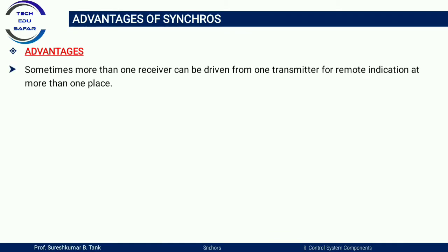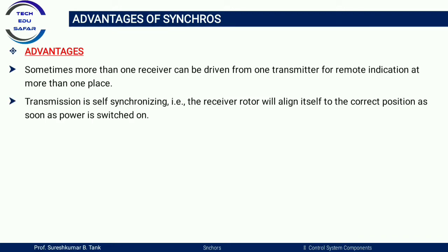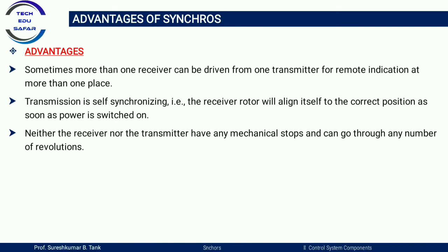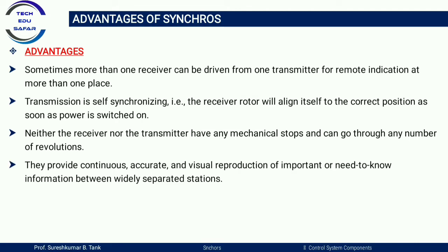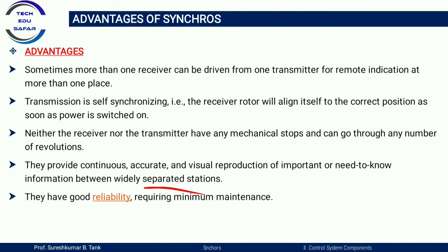The advantages of synchro are: first, more than one receiver can be driven from one transmitter for remote indication at more than one place. Second, transmission is self-synchronizing — the receiver rotor aligns itself to the correct position as soon as power is switched on. Third, neither the receiver nor the transmitter has mechanical stops and can go through any number of revolutions. Fourth, they provide continuous, accurate, and visual reproduction of information between widely separated locations. Finally, synchro has very good reliability and minimum maintenance requirements.